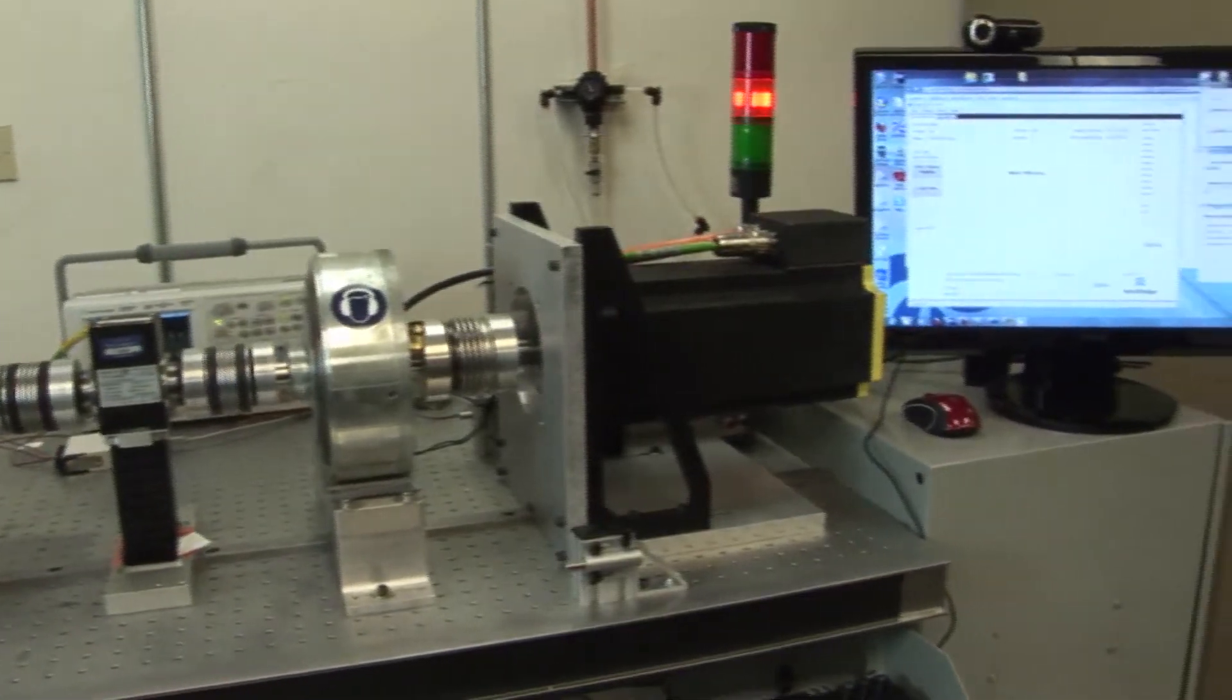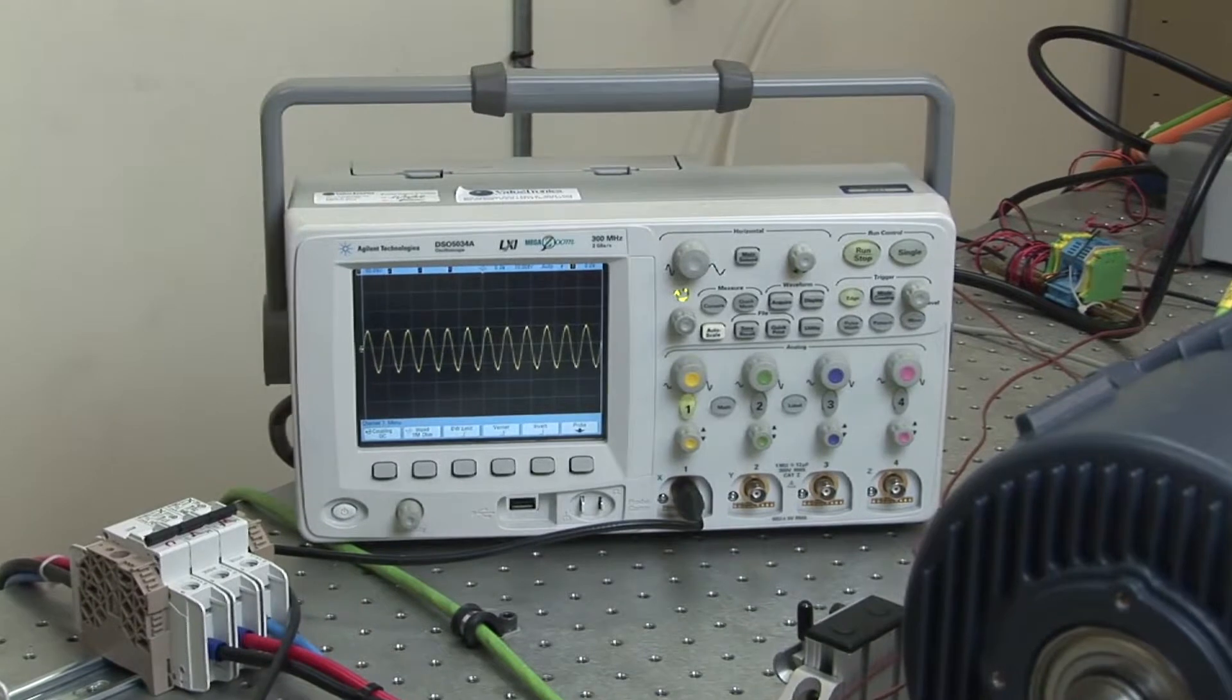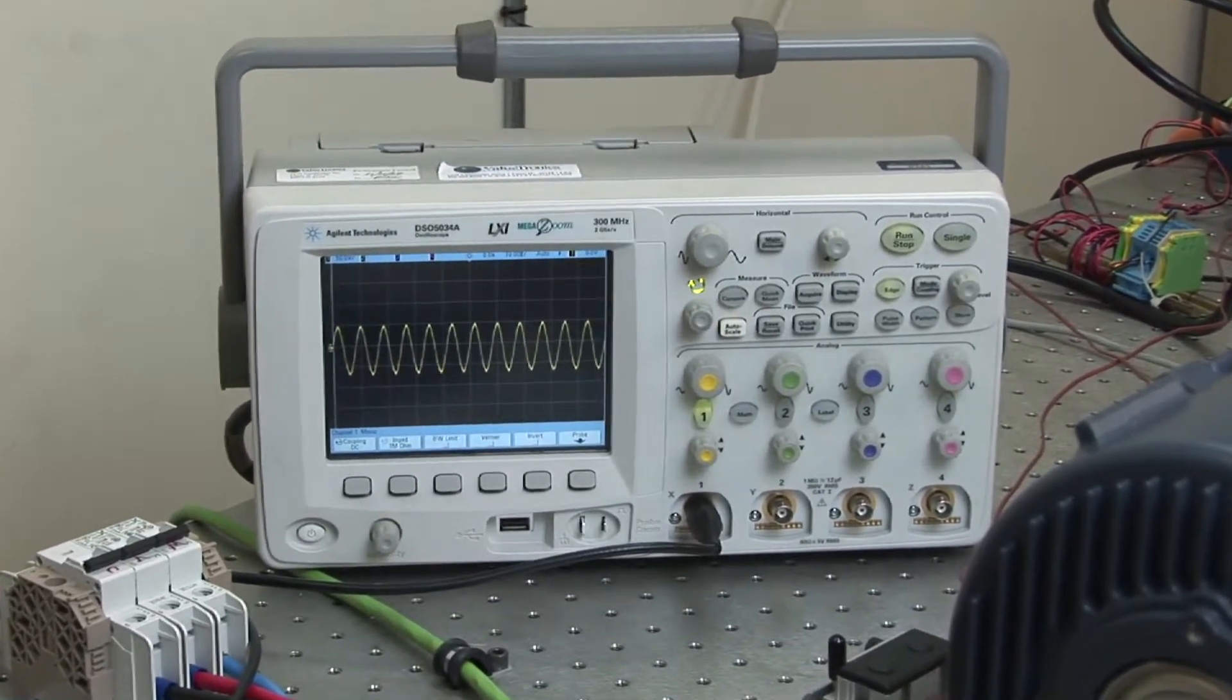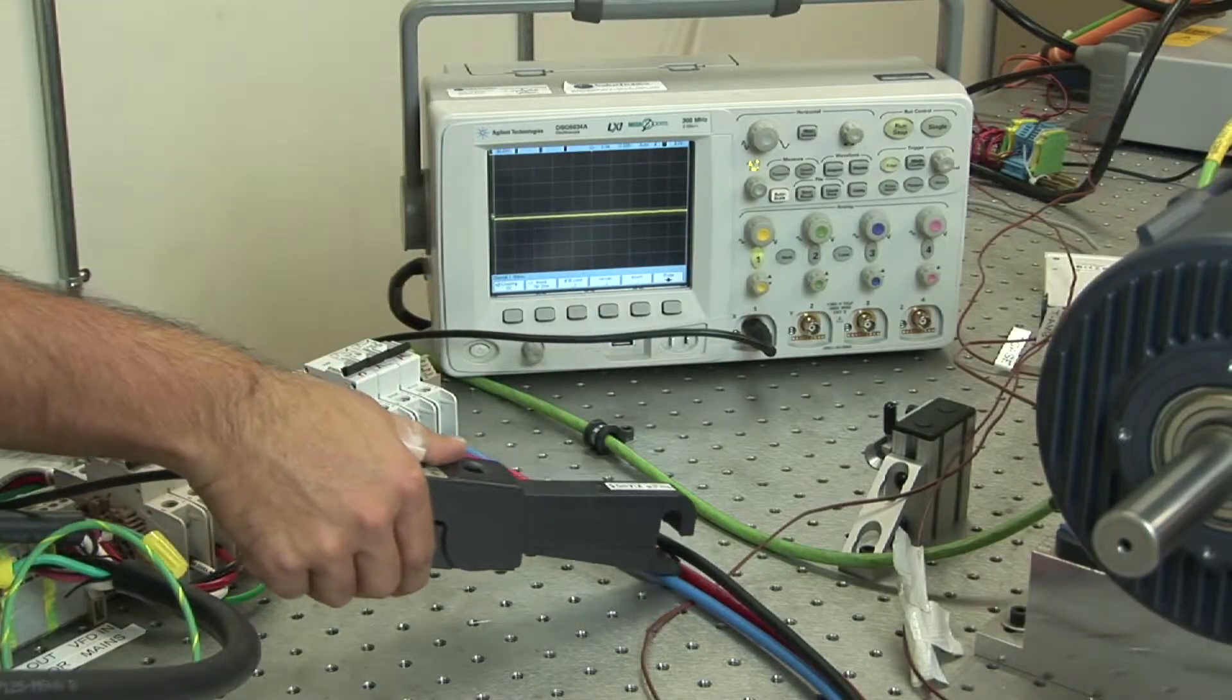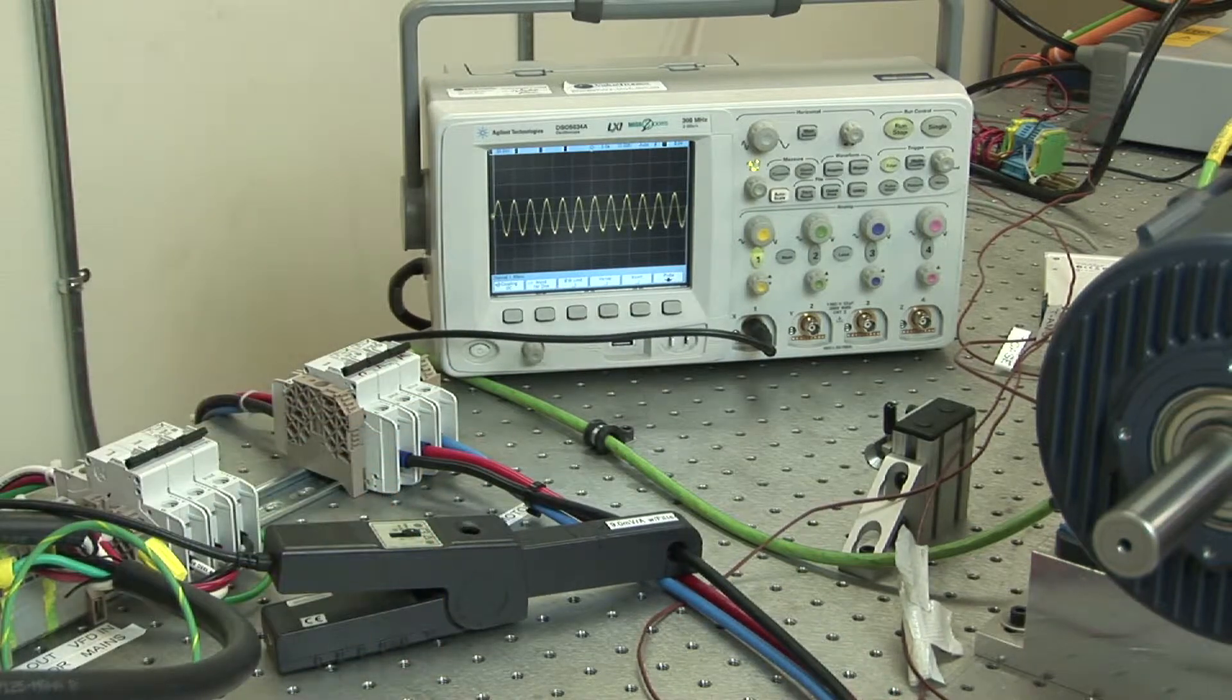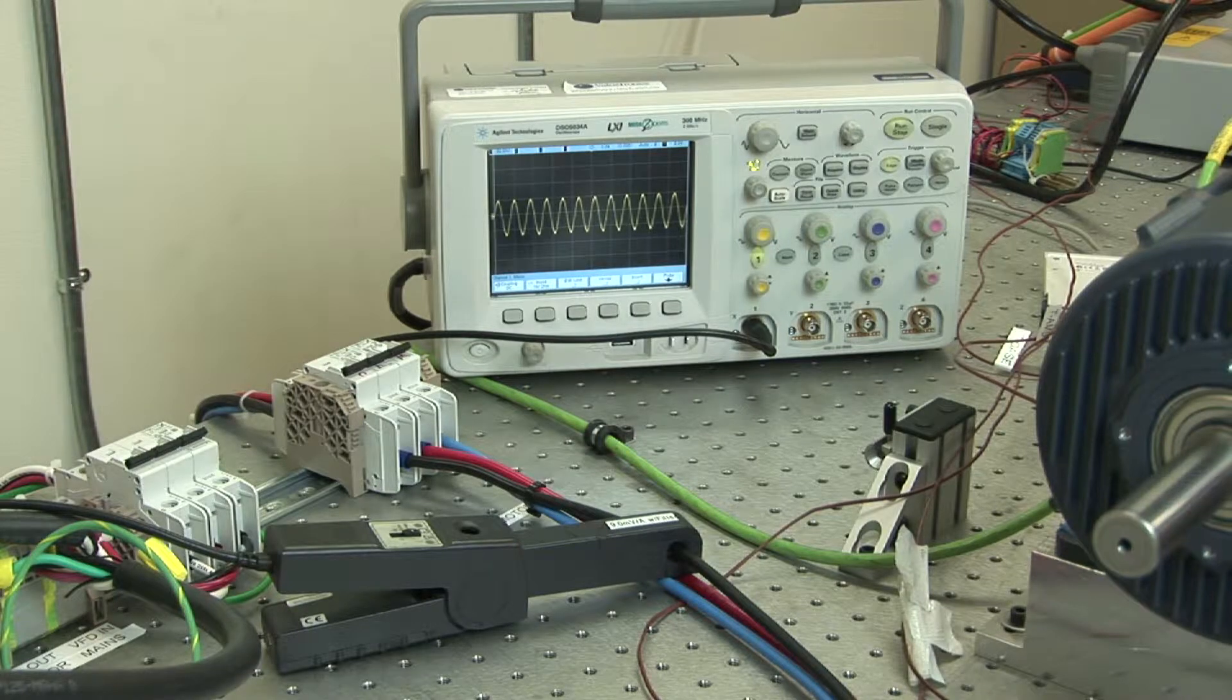This test station is supplied with 230 volts and 460 volt power inputs and can be used for both low and high voltage tests. Attaching an oscilloscope current probe to a motor phase input allows us to observe the power signal to the motor. This can help analyze performance and optimize drive tuning.